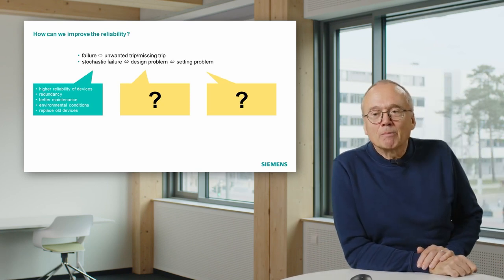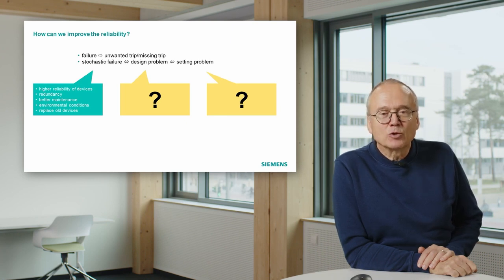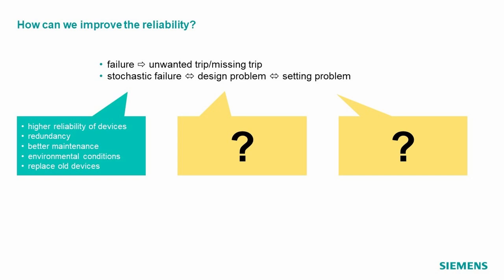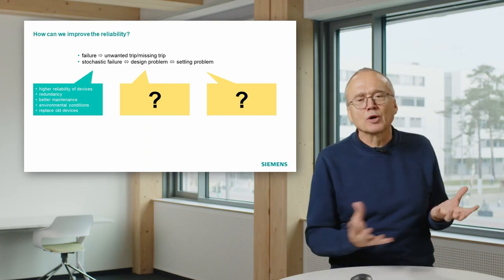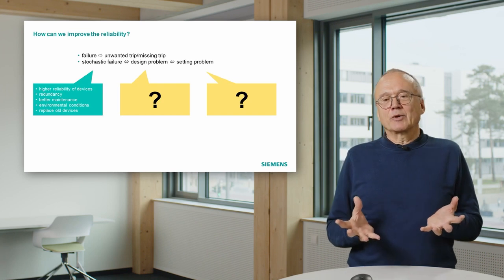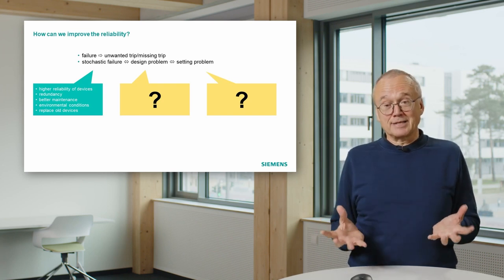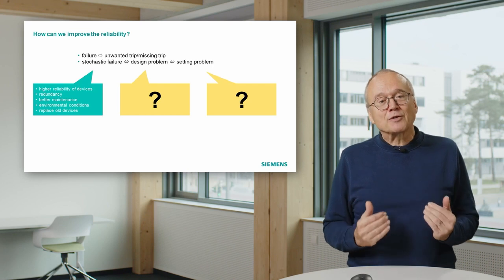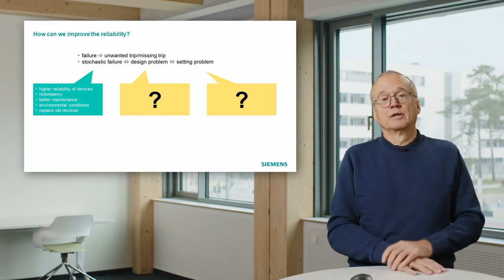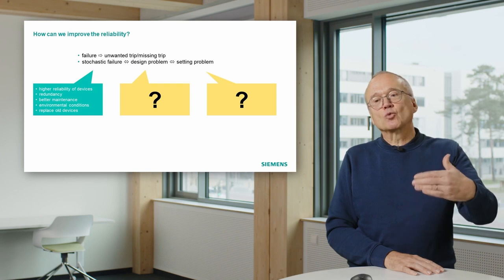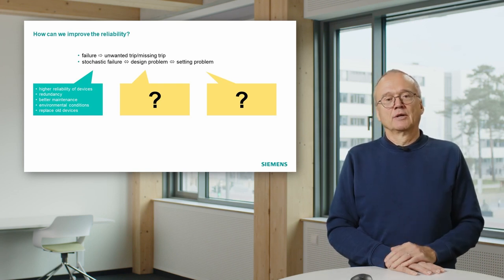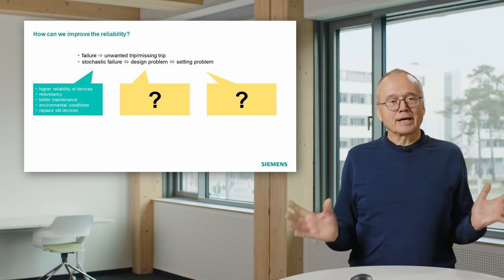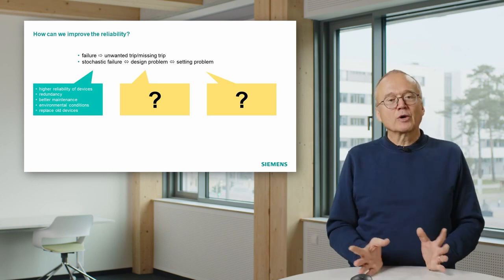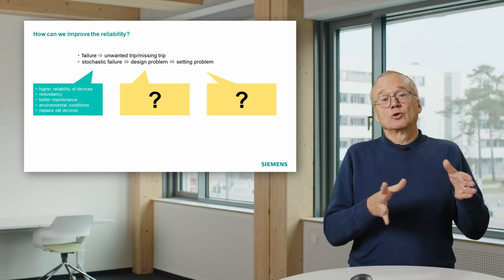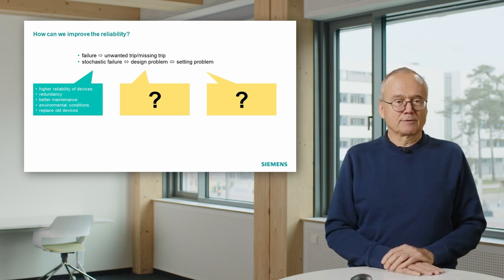Another thing is the environmental conditions. Where are the relays installed? And I can tell you, I've seen relays where you couldn't see any colors on the components. So they were installed in a dusty area, or you even may have corrosive gases there. And of course, if you have these conditions, the relay will work, but after some time you will have an increased failure rate. And you have to take that into account, or you have to think about, does it make sense to install the relays in a better place?